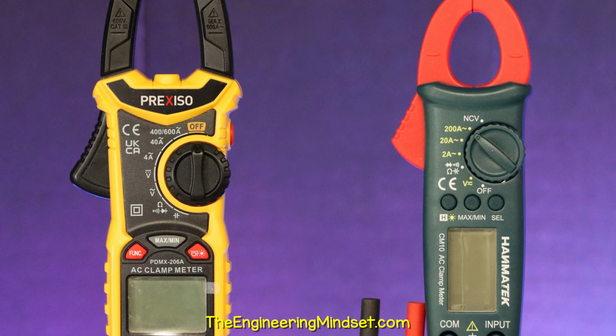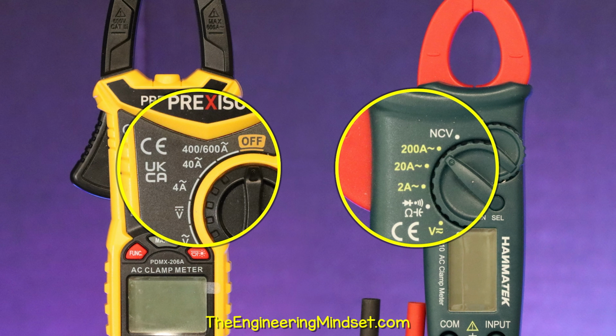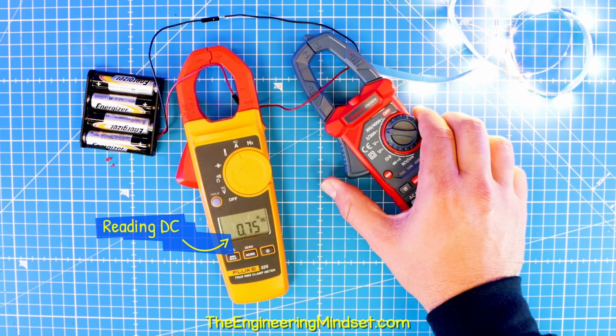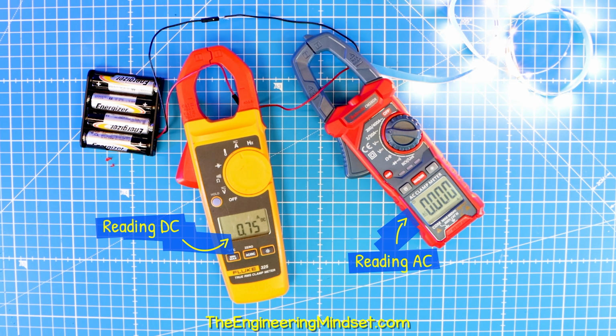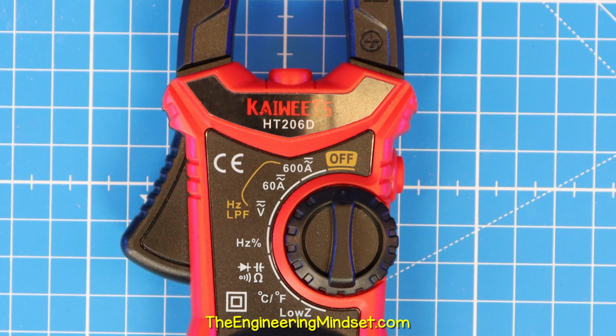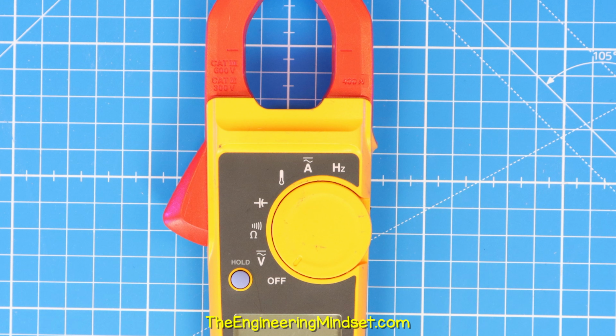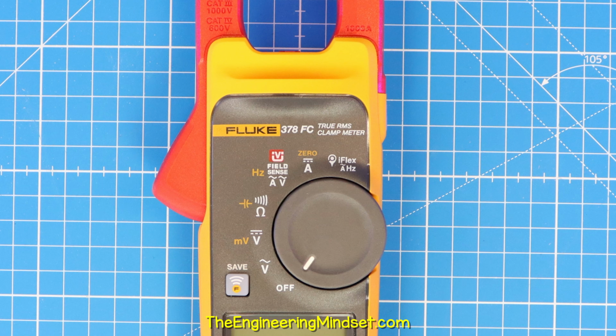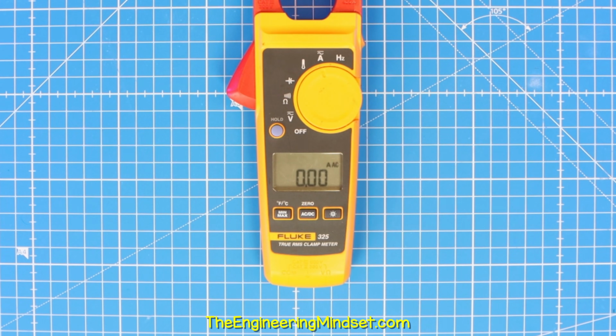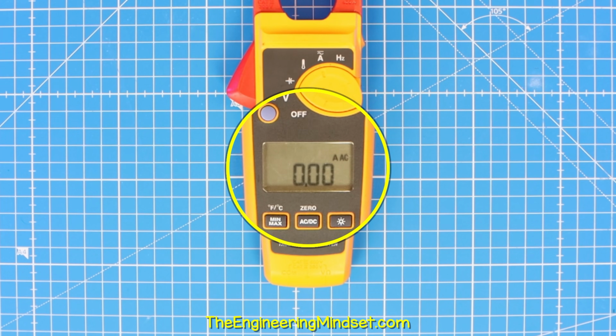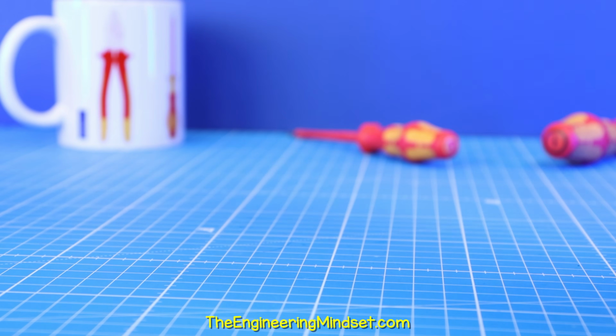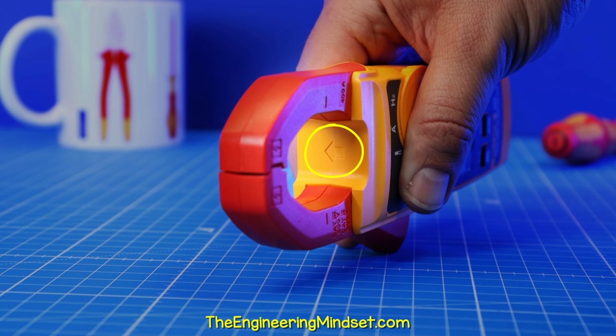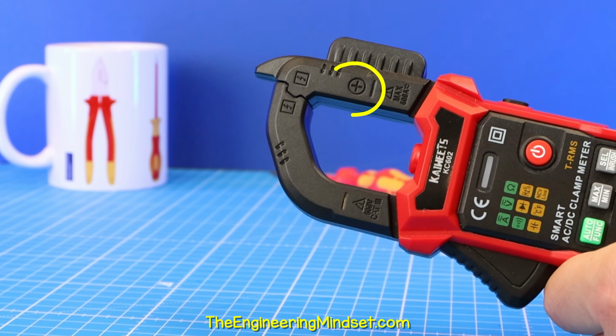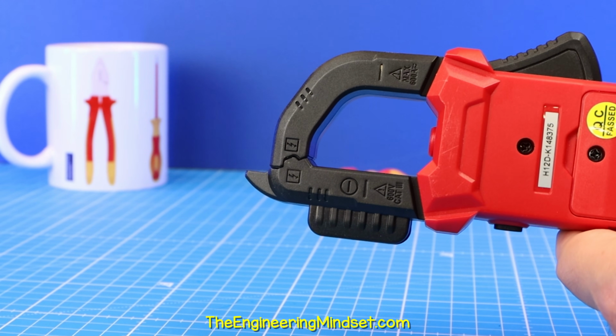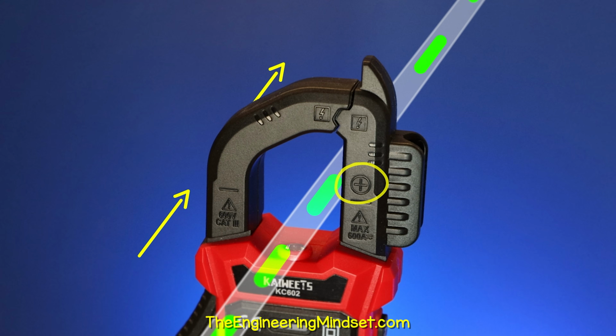If your meter only has the symbol A with a wavy sign like this, then your device can't measure DC current. You can try, but it will only show 0 amps. However, if your device shows a wavy line and a straight line, or a straight line and a dashed line, then you can measure DC current. The screen should also indicate that it's in the DC function. You might need to press the button to switch between AC and DC. Notice that there is an arrow between the Fluke clamp jaws. Other brands will use a plus and minus symbol on the clamp jaws. These just indicate the direction of current flow.